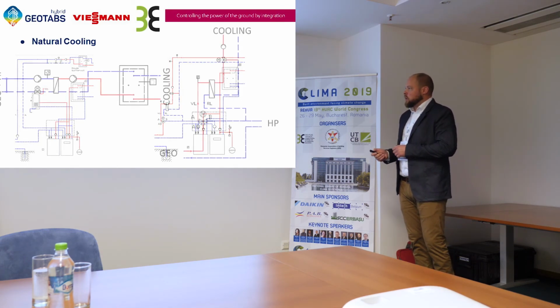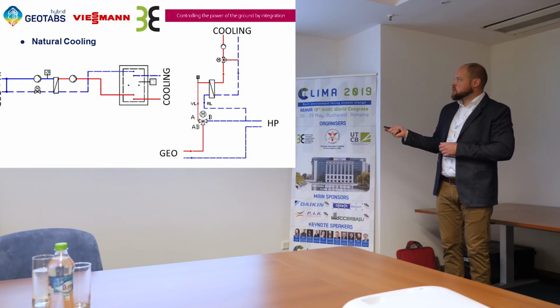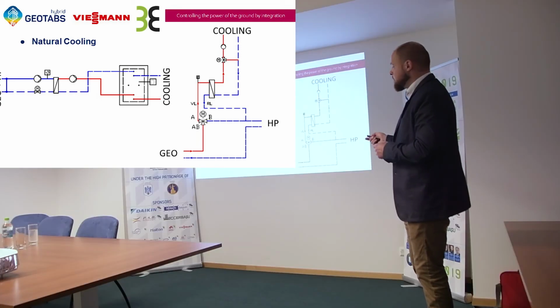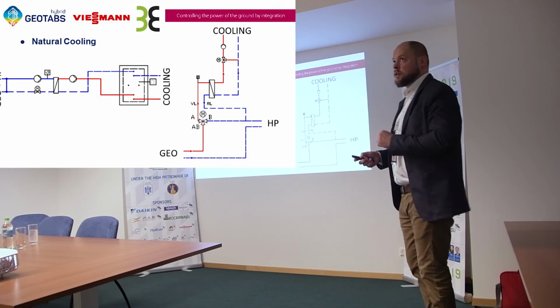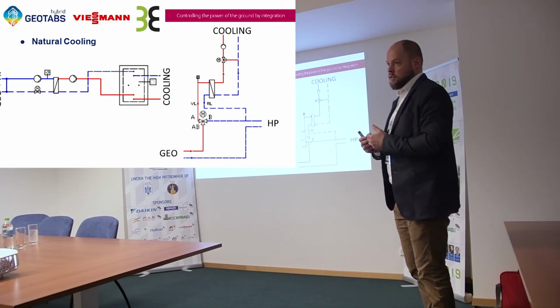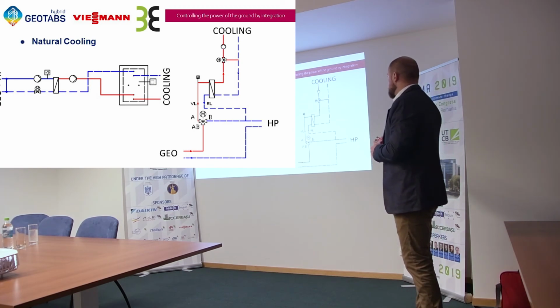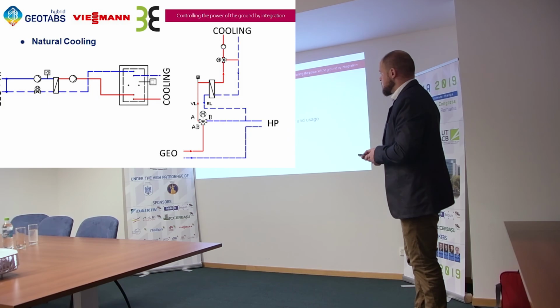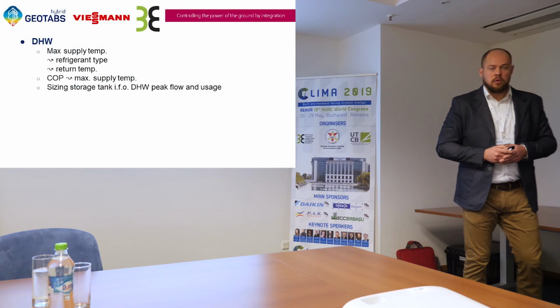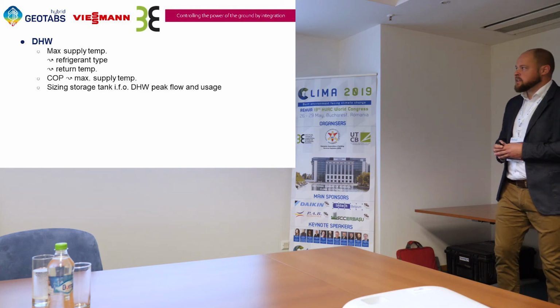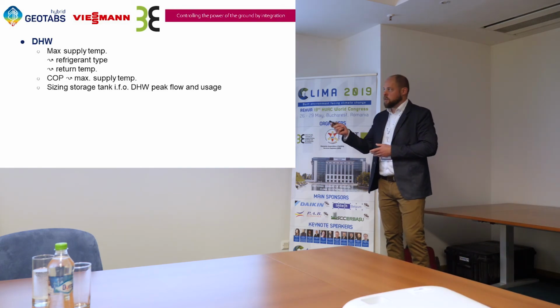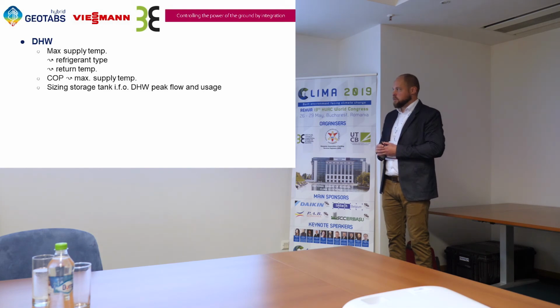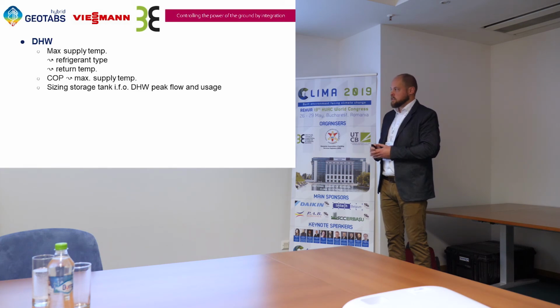So that's an option. We can also control the temperature to the building with a mixing valve here, because the source temperature can be 10 degrees, for example. If we send 10 degrees to ceiling systems, we have condensation, so that has to be avoided, and we can do that with this mixing valve. So that's an option. Then finally, domestic hot water. The maximum supply temperature depends on the refrigerant type we use, and also the return temperature inside the system. And the COP, of course, also depends on the supply temperature needed inside the domestic hot water tank.